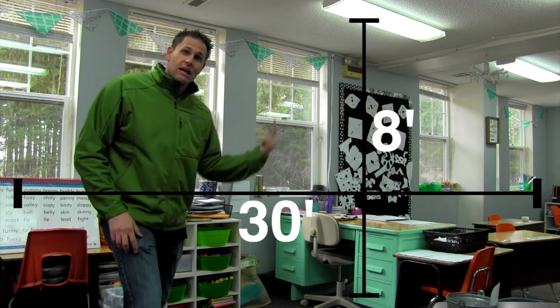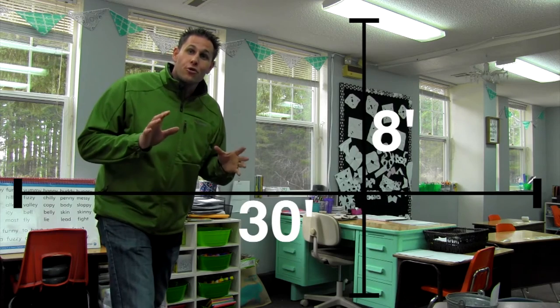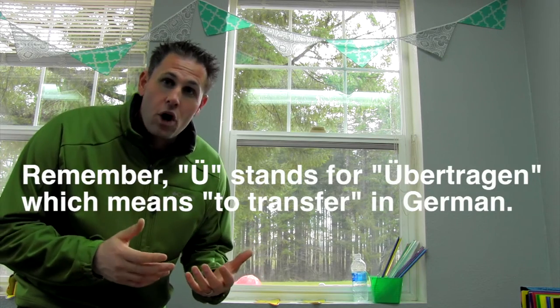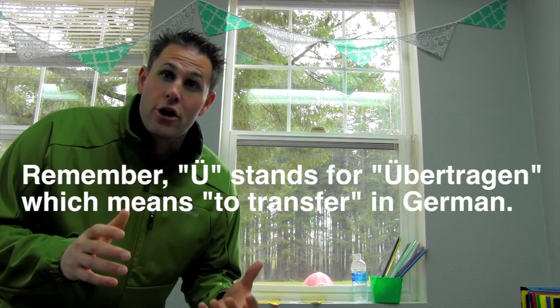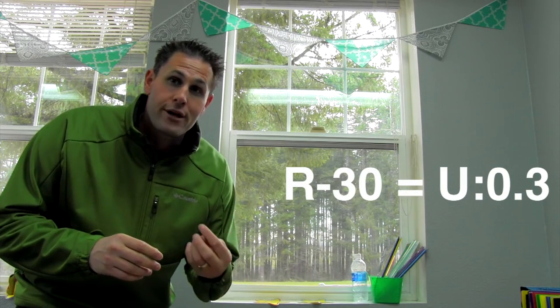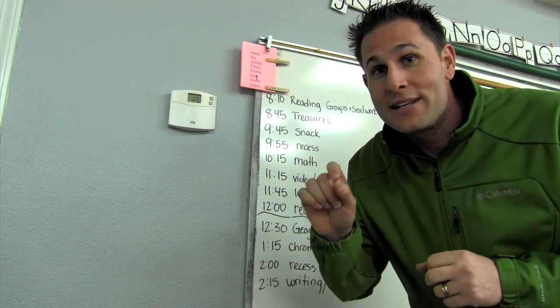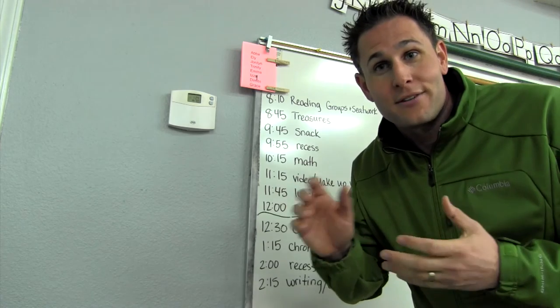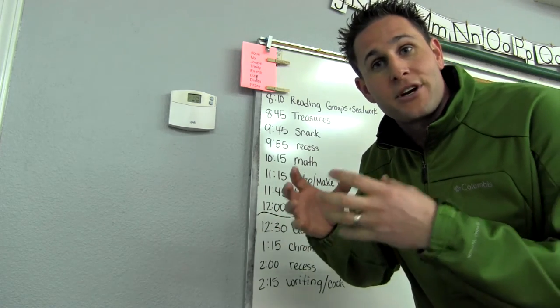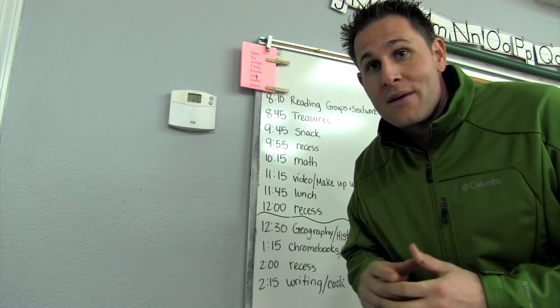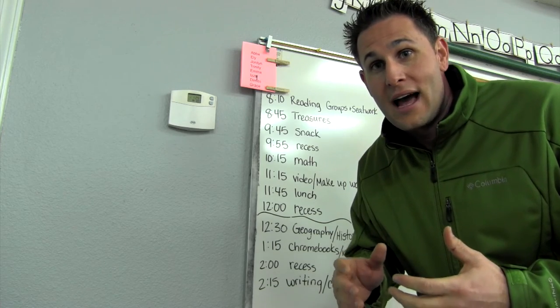Let's use this classroom wall for example. It's about 30 feet long and about 8 feet high, for a total area of 240 square feet. Each surface and material has a different U value. When you think about a wall that's insulated to perhaps an R30, that has a U value of 0.3. For our example, we'll just pretend that this is a solid wall that is pretty well insulated. Now remember, we're talking about difference in temperature, or delta T — the difference of temperature inside and outside. And in the wintertime, it's going to be colder outside.